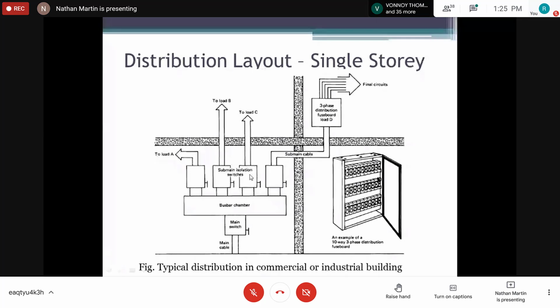So this is like a subdivision or multi-story, where this might be the separation of a floor, right, and load B to load C might be a different floor, and we have a sub-main to a sub-main panel here, right? So this is one type of arrangement that you can have. So it would come into our main switch, or this would be our bus bar chamber. Our bus bar chamber will be connected to our different isolators, and then we can isolate the different panels. So this might be supplied to different sub-panels, right, in a single story layout.